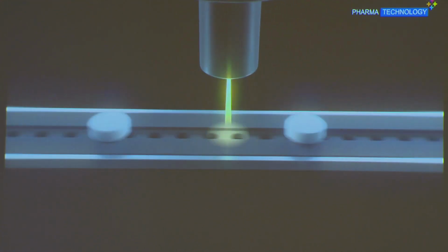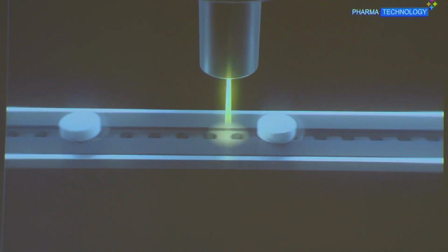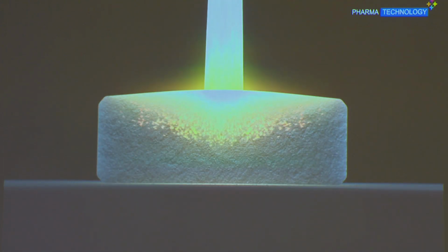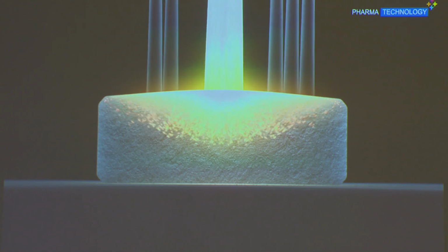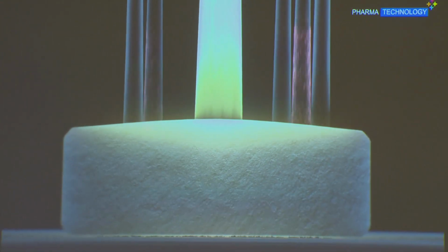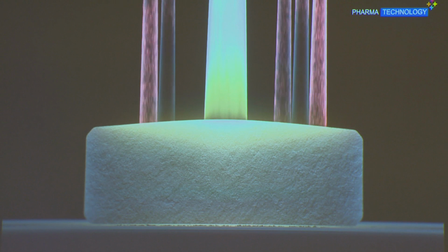Then, the product enters the NIR SRS measuring chamber, where the NIR infrared beam penetrates the surface of the tablet and collects spectral information about the API. The re-emitted light is picked up by 9 optical fibers and transmitted to the spectrometer. The obtained spectra are converted into an API's fraction with the use of a chemometric model.